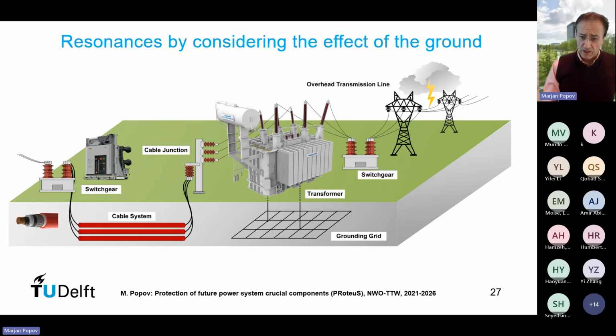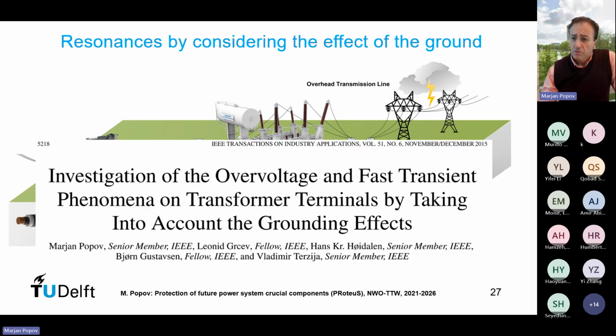However, once we start thinking about developing protection methods against these resonances, we must be very sure that everything we simulate is correct. All the components in this case must be modeled in a broad frequency range, depending on the phenomena. Normally, lightning phenomena are one of the fastest, which may have up to 1 megahertz or above, depending on the rate of rise of the lightning current. Also, all other components need to be very accurately modeled.